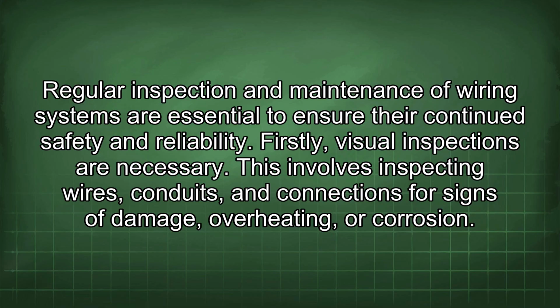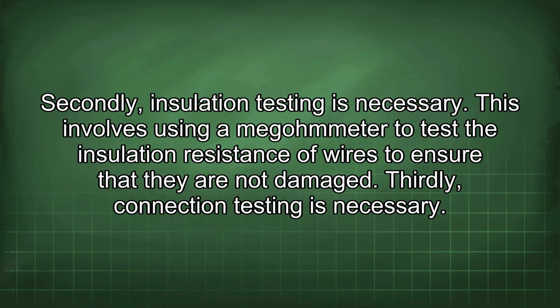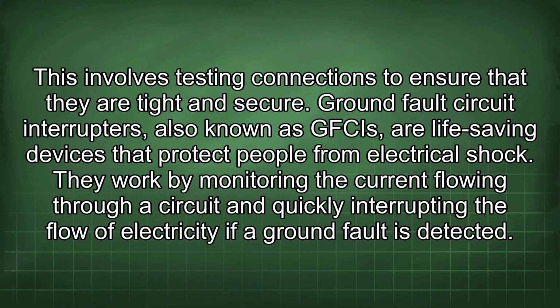Firstly, visual inspections are necessary. This involves inspecting wires, conduits, and connections for signs of damage, overheating, or corrosion. Secondly, insulation testing is necessary. This involves using a megohmmeter to test the insulation resistance of wires to ensure that they are not damaged. Thirdly, connection testing is necessary. This involves testing connections to ensure that they are tight and secure.